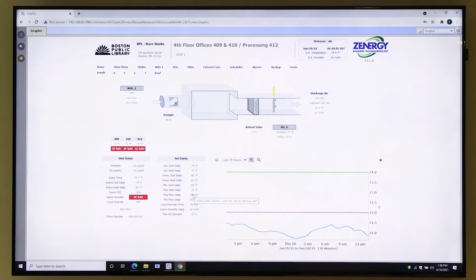That's your cooling. For heating, as you drop below your heating set point, that reheat valve is going to modulate open to try and heat the incoming air to the space so that you can heat the space. The other thing that this is going to be responsible for, if it exists with the unit, is the humidifier. So in spaces that have humidifiers, they are looking for, by default, that 50% humidity level in the space. That doesn't appear to be always attainable, obviously, because we're not getting there right now.